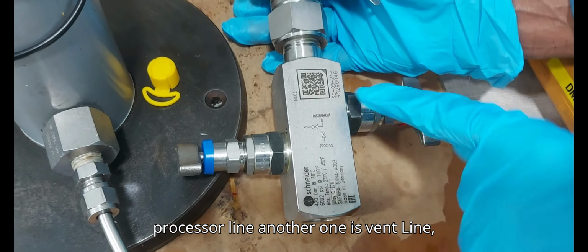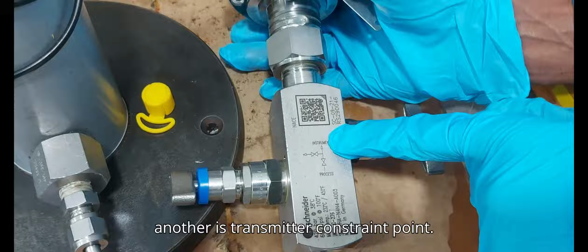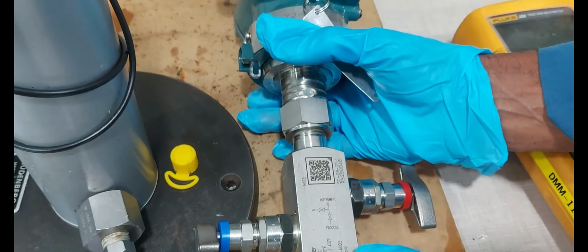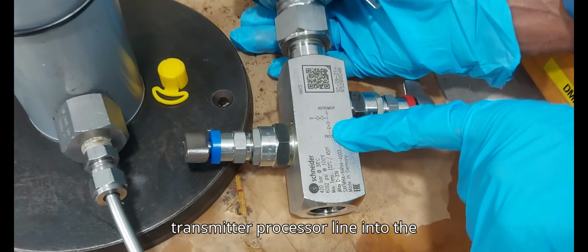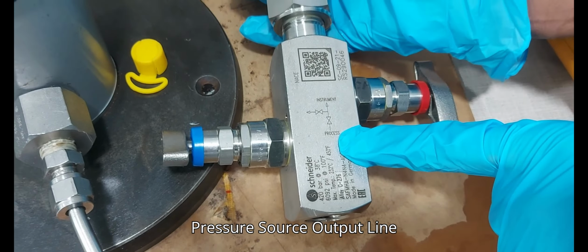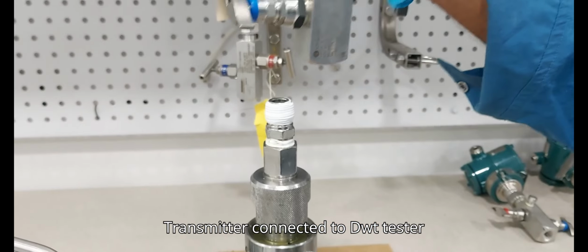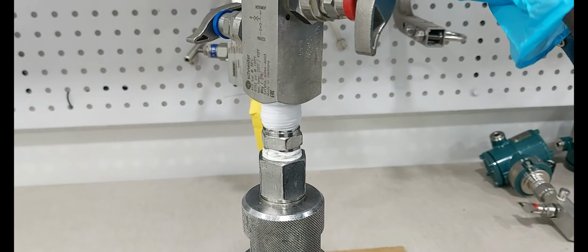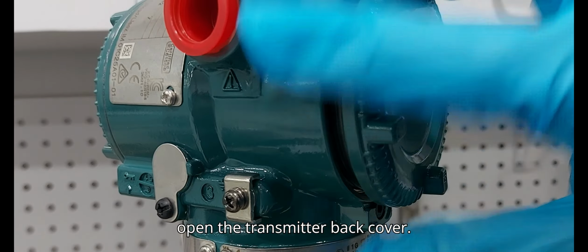This is a process line. One is the vent, and this is the transmitter connection point. Next we are connecting the transmitter process line to the dead weight tester output line. The transmitter is connected to the dead weight tester output line. This is the transmitter back cover.